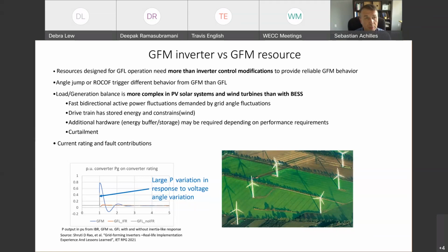That power and that energy has to come from someplace. So one of the challenges to have a grid forming resource is to have enough of that power and energy available in the time frame required. In the case of wind turbines, as mentioned before, you can potentially use the drivetrain, which is rotating and has energy stored there, to temporarily extract energy. There are some limitations though: you cannot exaggerate how much energy you extract from the drivetrain without risking tripping on underspeed or causing torsional issues in the equipment. The other way of doing this is with curtailment, which is painful, as everybody knows.